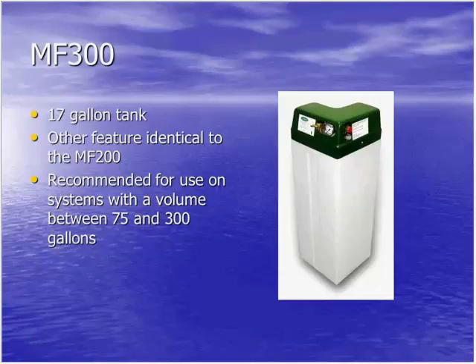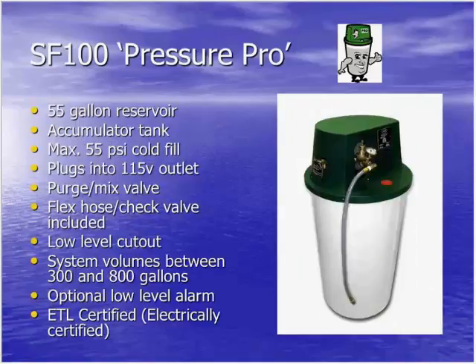This SF100 Pressure Pro is our most commercial size unit. Comes with a 55-gallon reservoir and an accumulator tank. It has a maximum fill pressure of 55 psi, which is good for up to about a 10 or 12 story building, depending upon how many feet per story you have in that building. And it's an adjustable range from 5 up to 55 PSI. It comes preset at about 12 PSI, I believe.